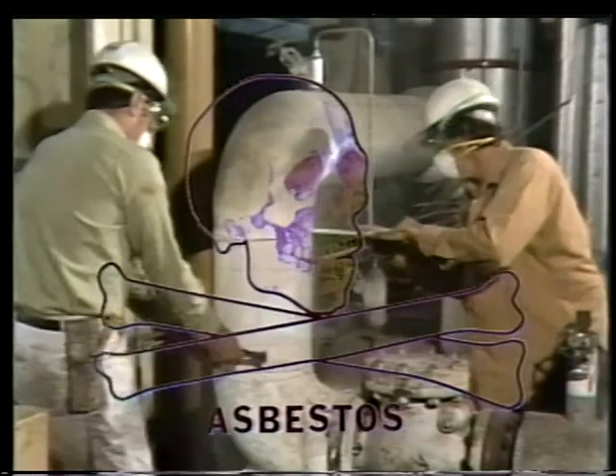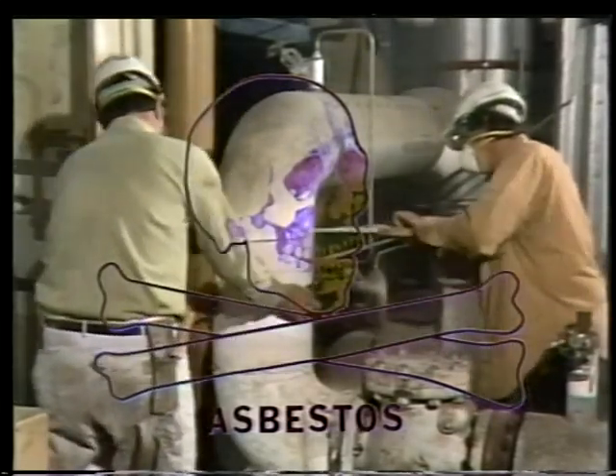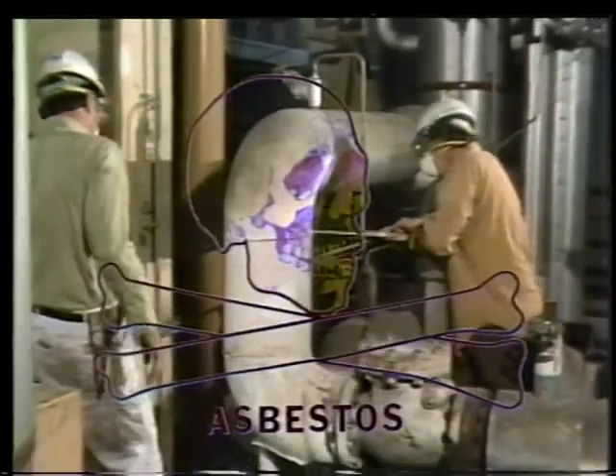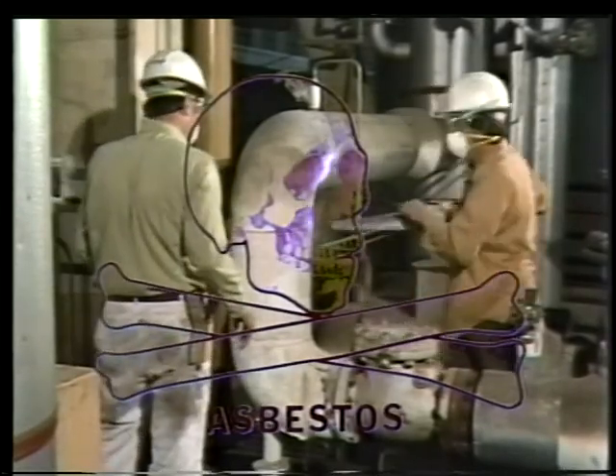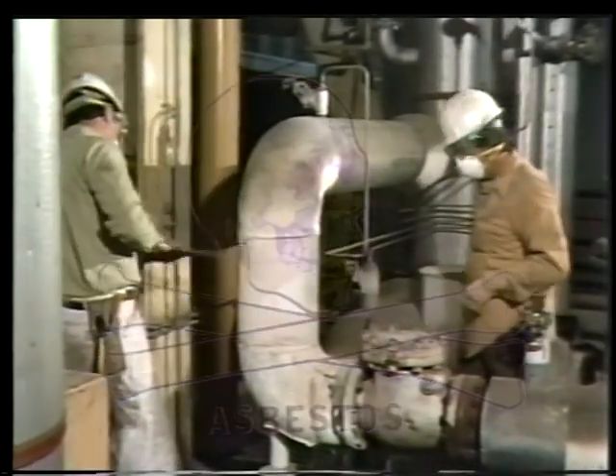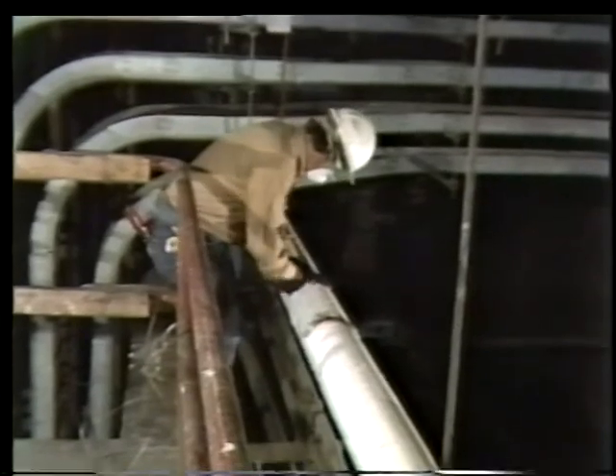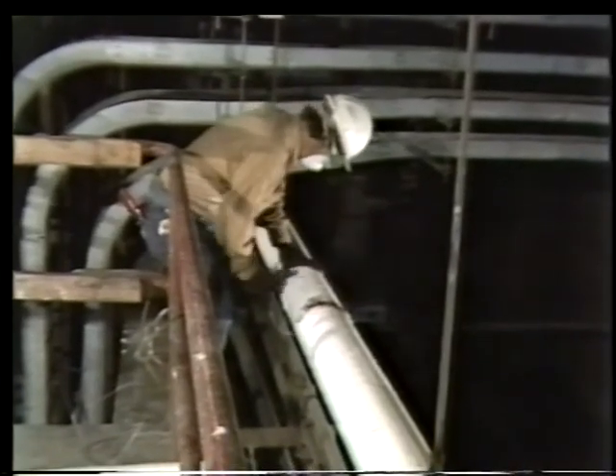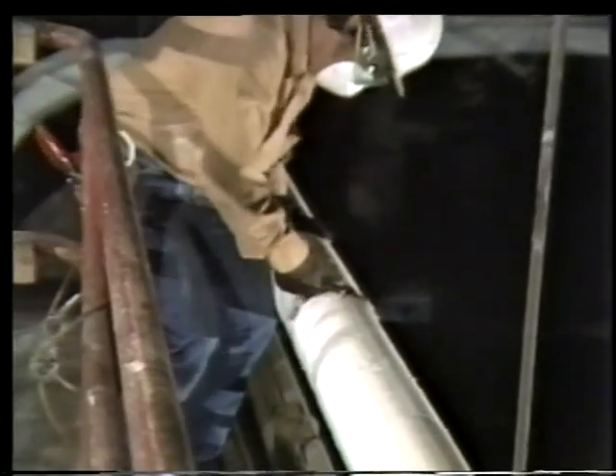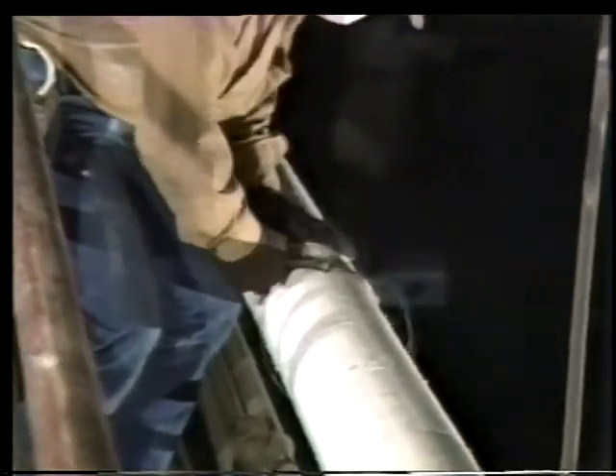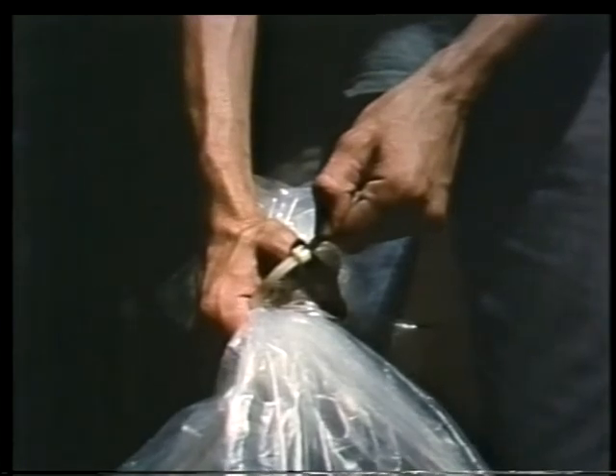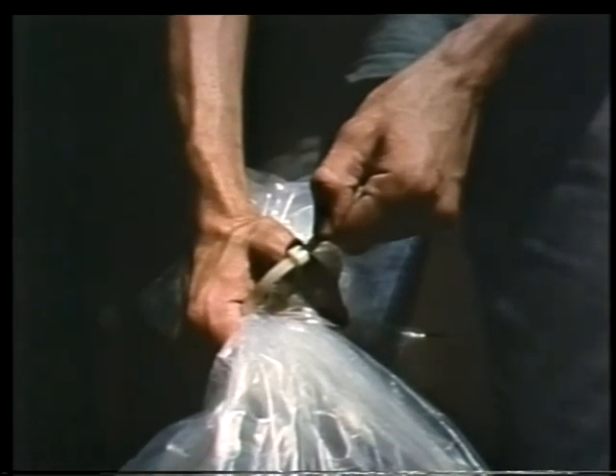It's no longer used in insulation, but if you're going to be repairing or ripping down older insulation systems, you may be in contact with asbestos. Wherever you might be working with asbestos, use all the precautions you can to keep it out of your lungs. Dispose of scraps and used insulation properly. They should be removed in sealed plastic bags. When you're done, vacuum the floor and your clothes to prevent spreading asbestos dust around.